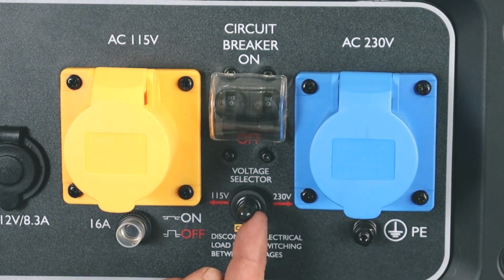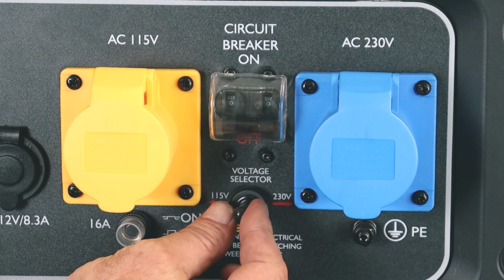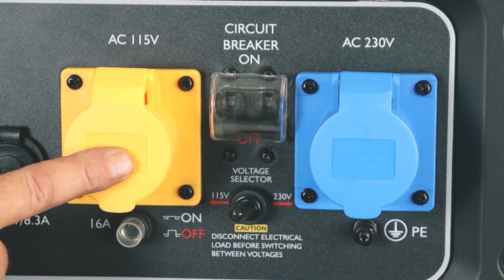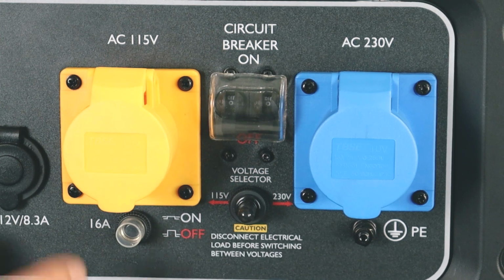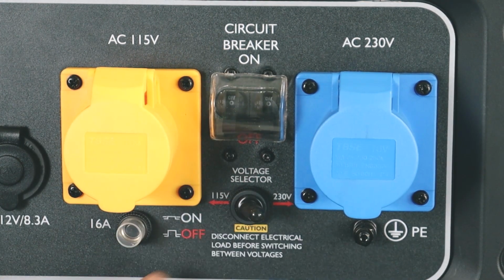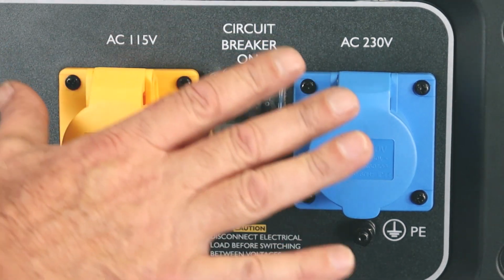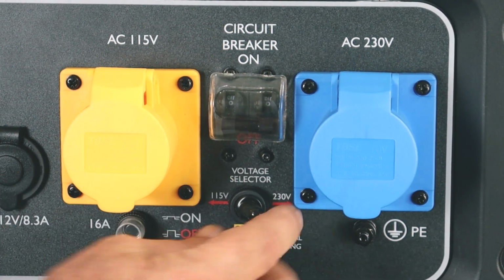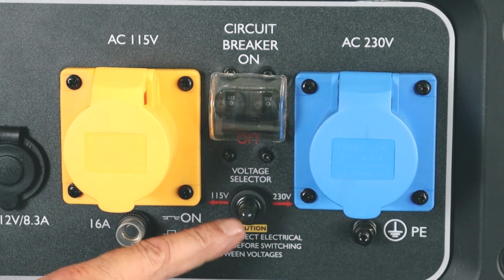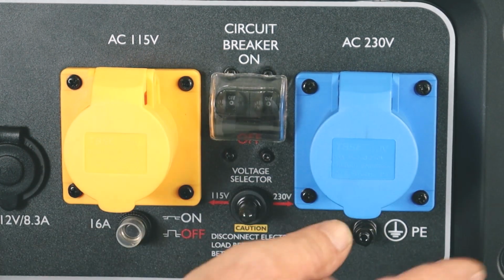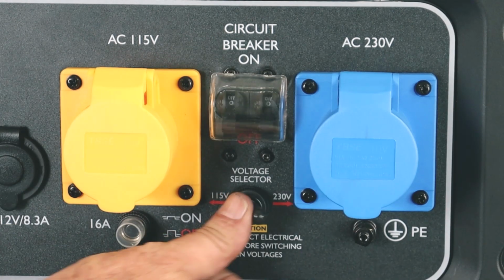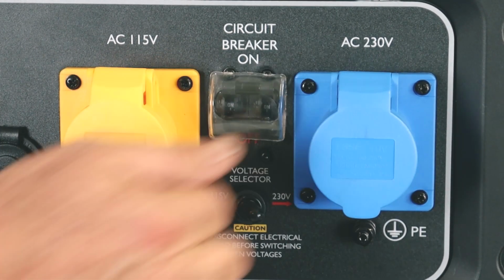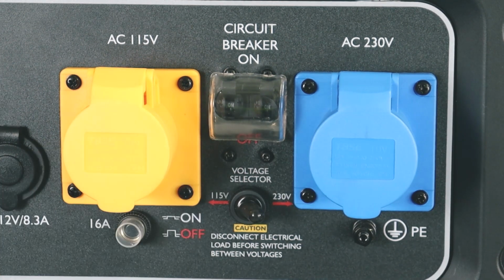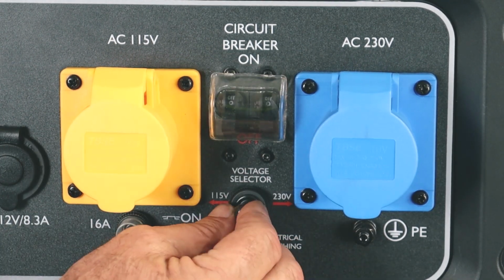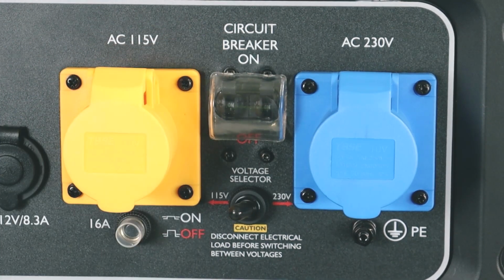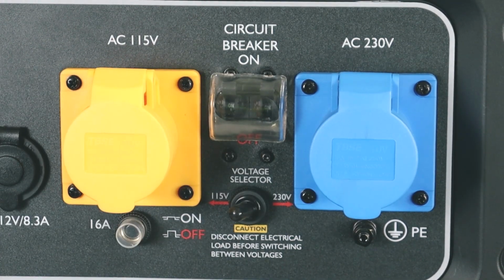So what we've got here is the toggle switch. Now this is three positions. This way, as you would imagine, would be when you're using 115. The central will give you no output from either. This way will give you 230. Best if you're changing from one to the other, or if you've got it in the center, don't use this to remove the load. Use the main breaker. So if we're switching between, main breaker off, change to 230, plug our appliance in, switch the main breaker on. And the same to go back to 110. Main breaker off, change to 110, turn the circuit breaker on. That's always very good practice.